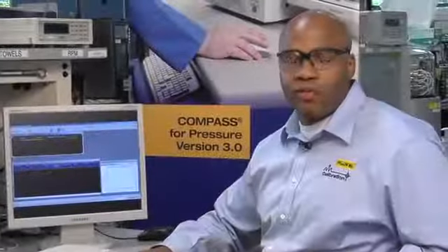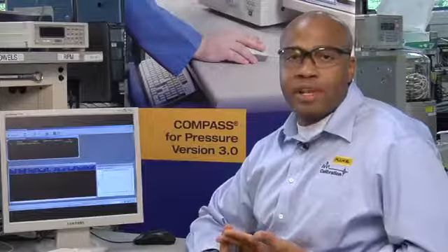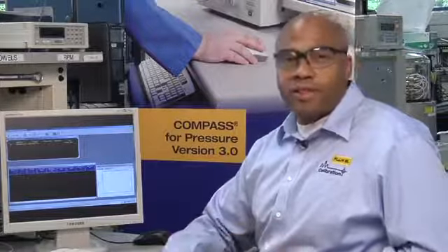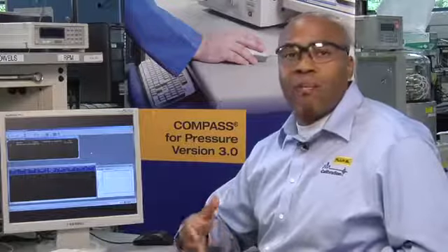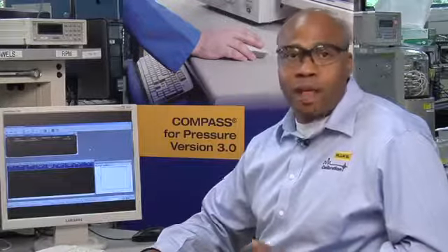Compass includes several device editors. There's a DUT editor, support device editor, and the piston gauge platform editor. Each of these editors can be controlled by rights management, so if you choose, you can have a lab manager define who can access which feature when. So this is designed to comply with regulatory compliance issues.